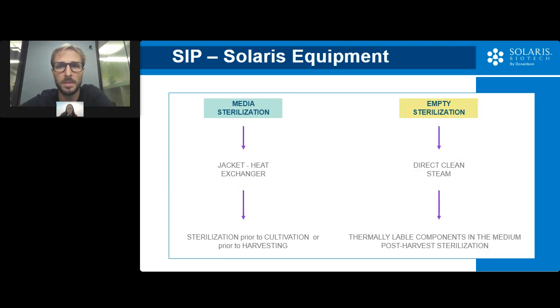A couple of slides ago, we mentioned different methods for sterilizing an SIP bioreactor. During the media sterilization, the steam will flow through a heat exchanger and heat up water in a closed-loop recirculation jacket. The heat will be transferred to the vessel and will reach the desired temperature. This is used, of course, to sterilize the cultivation medium prior to the inoculum, but could also be really helpful when working with BSL-2 microorganisms or higher. In fact, we can just inactivate the microorganism in the bioreactor prior to harvesting.